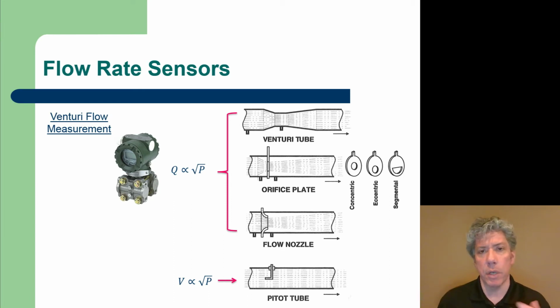However, the Venturi tube has nice pressure recovery. In other words, the pressure at the entrance to the tube is at whatever level it's at, and then it goes down in the throat of the Venturi, but then it recovers and comes back almost to where it was before if the Venturi is designed right. In an orifice plate, usually the pressure recovery is very small. Rather, there's a lot of pressure loss, and that's a permanent change. What that translates to is needing more pumping power to keep the flow going.